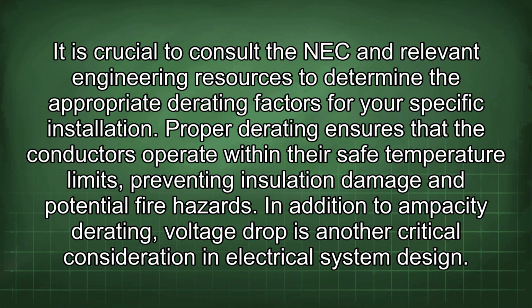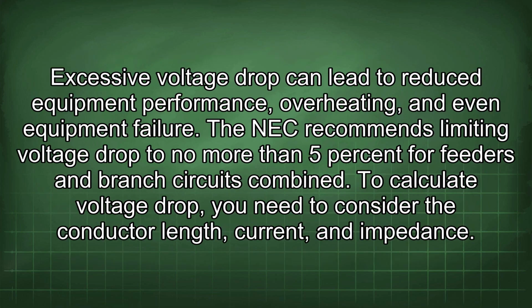Proper derating ensures that the conductors operate within their safe temperature limits, preventing insulation damage and potential fire hazards. In addition to ampacity derating, voltage drop is another critical consideration in electrical system design. Excessive voltage drop can lead to reduced equipment performance, overheating, and even equipment failure. The NEC recommends limiting voltage drop to no more than 5% for feeders and branch circuits combined.